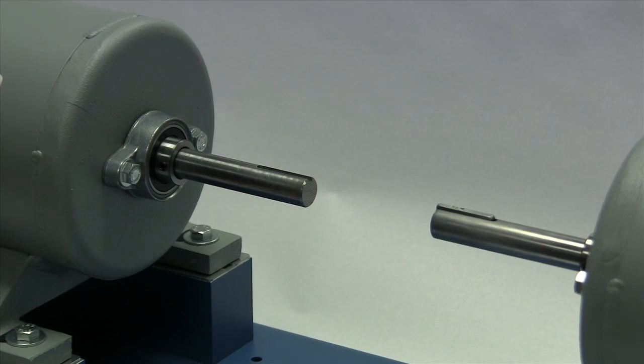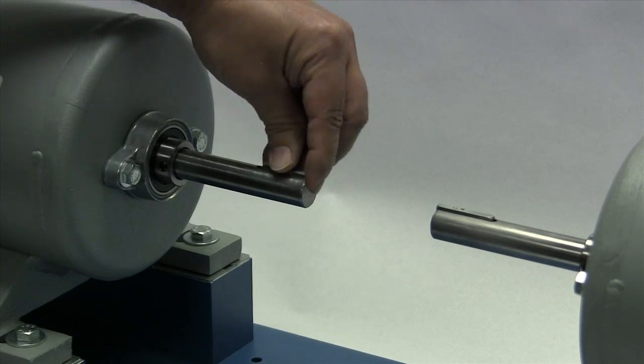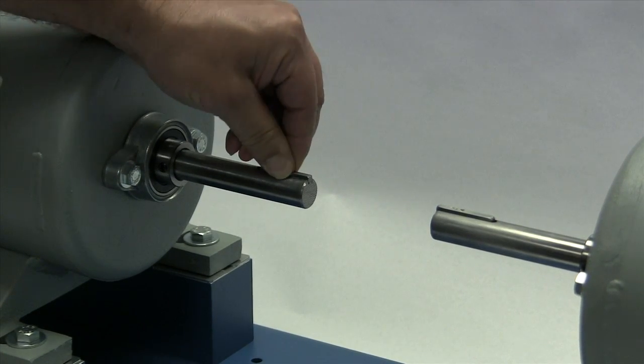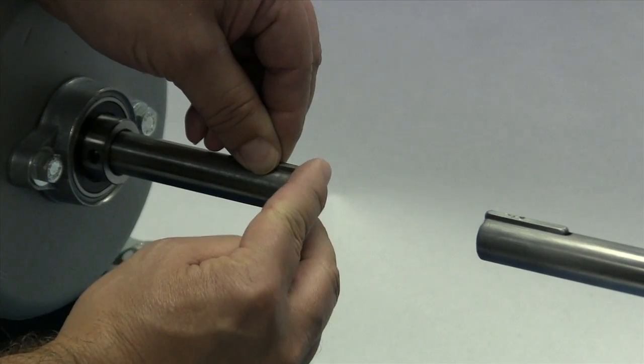Before installing the hub, place the key in the keyway on the shaft. The key should fit snugly into the keyway with no side-to-side movement. The end of the key should line up with both the end of the shaft and the hub.